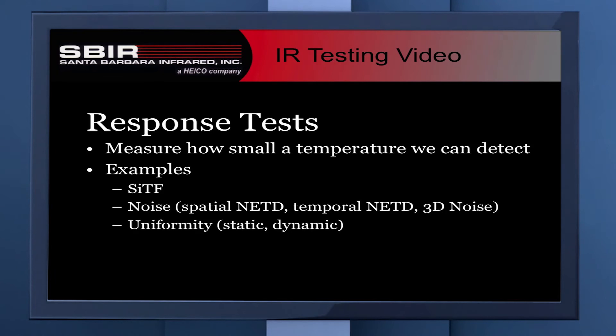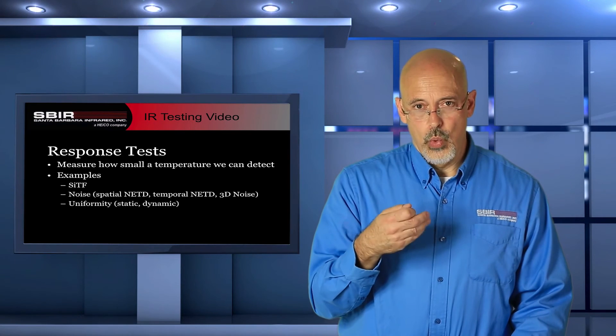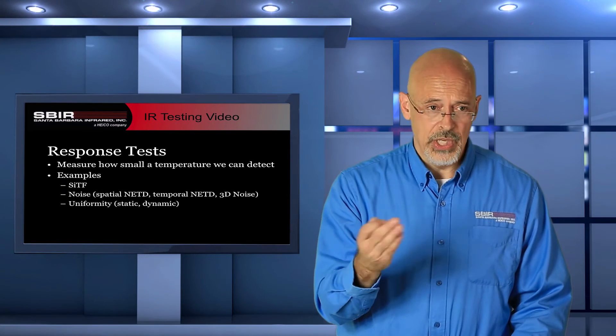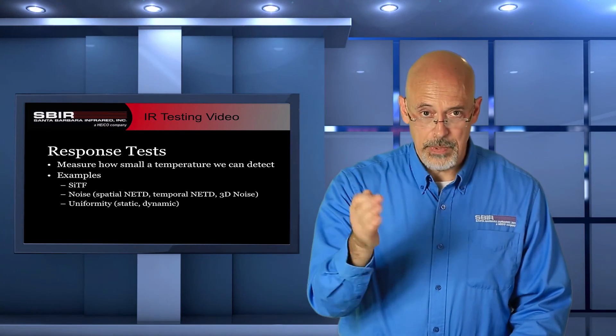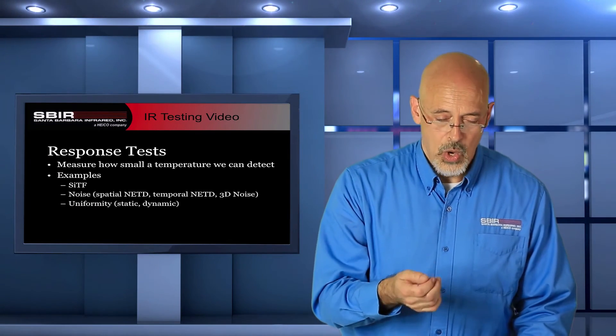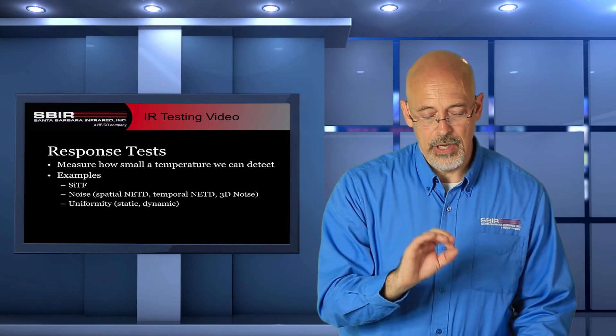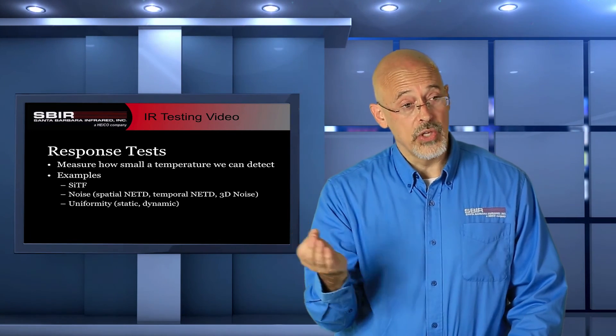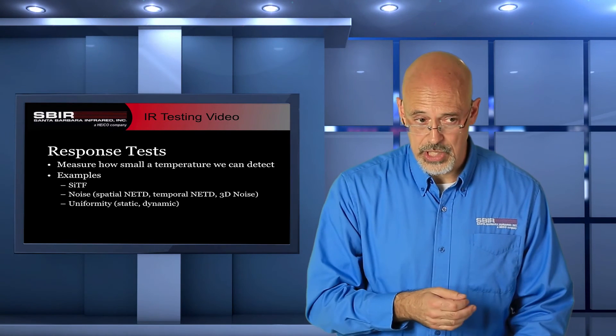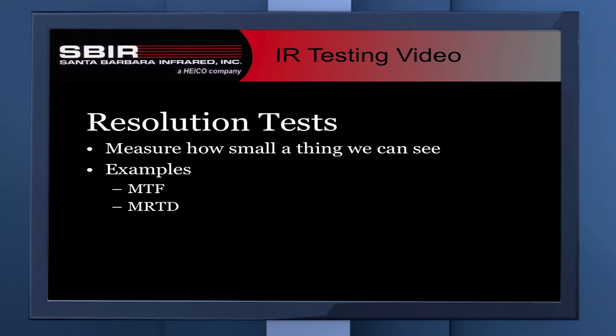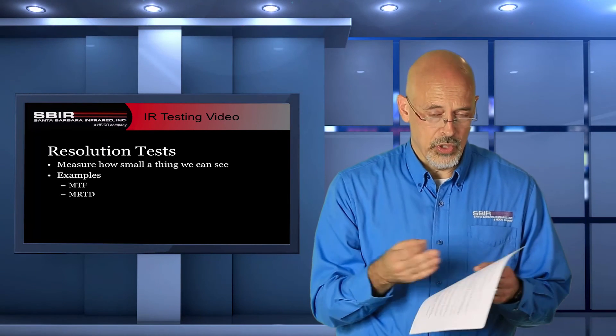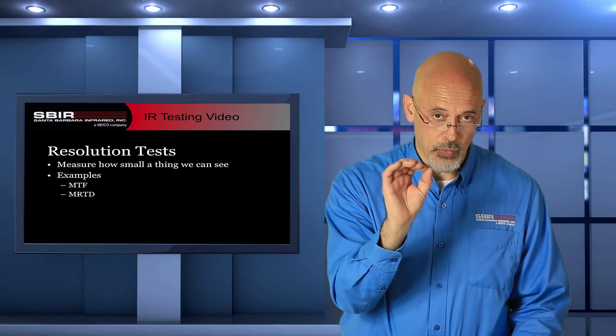Response tests are when you're measuring the way the camera responds to temperature variation in the infrared. When I change the temperature, I want to see how the camera responds — either in a straightforward linear response test like an SITF test, or looking at how small a temperature variation you can measure. That's when you're concerned about noise, and you have tests like NETD used for testing the noise on a camera. Resolution tests are when you're looking at how well a camera can see small things — how small can something be and still be resolved? This is concerned with tests like MTF and MRTD, used to determine the resolution on a camera.